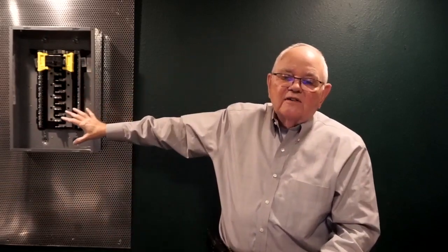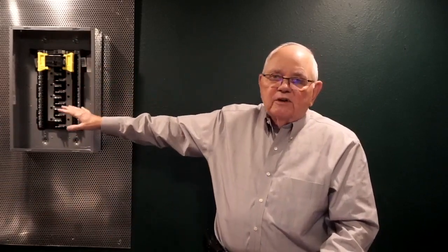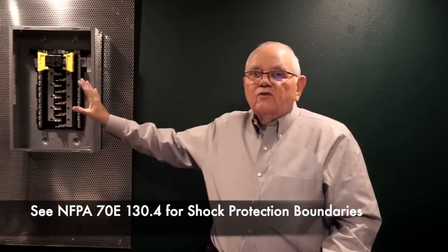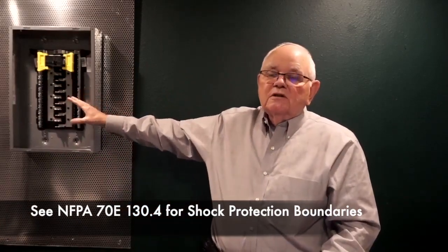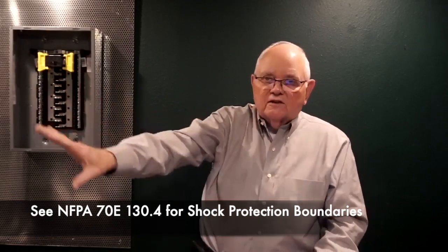And then we have boundaries. Boundaries are in my head right here. That's the only place they really exist, you see. So when I go to do work inside of this panel, I have to establish some boundaries. I have to know that my limited approach boundary, in other words, where a shock hazard exists, is at 3 feet 6 inches from a panel board like this, okay?